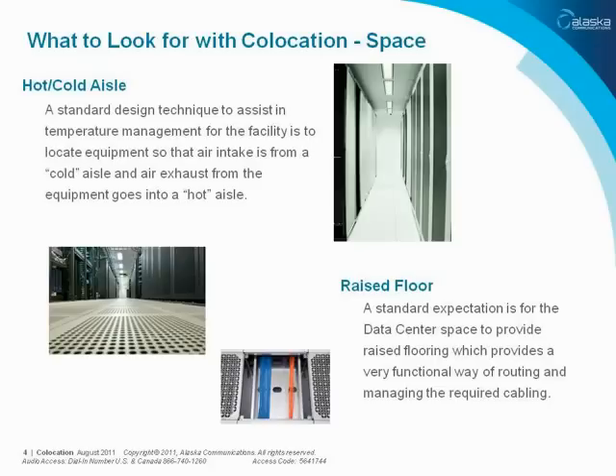The cold aisles have fans and delivery systems sending chilled air down the aisle. Equipment down the rows of cabinets faces so that the air intake fans pull air off the cold aisle, and exhaust goes out the back into a hot aisle, maximizing the cool temperature of the air going into the equipment to keep it at its ideal operating temperature.